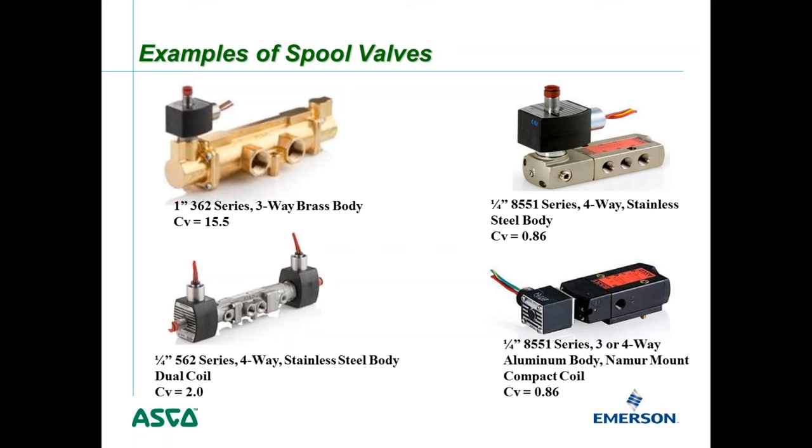In the upper right is a quarter-inch 8551 series four-way stainless steel valve with a CV of 0.86. On the bottom is another quarter-inch 8551 series Namur mount that can be configured as either a three-way or four-way valve by changing a small mounting flow pad. This version has an aluminum body and compact coil — a very inexpensive spool valve with good flow, handling smaller ball valve and butterfly valve applications.